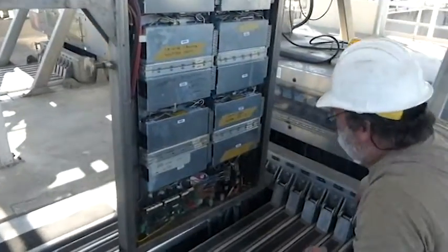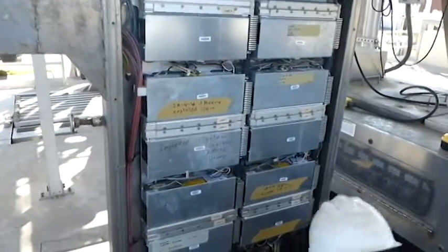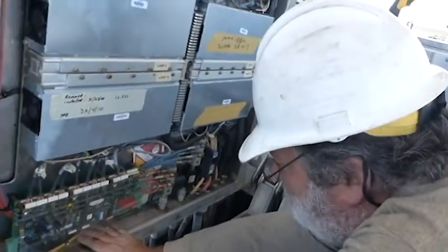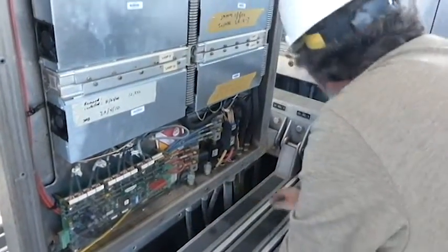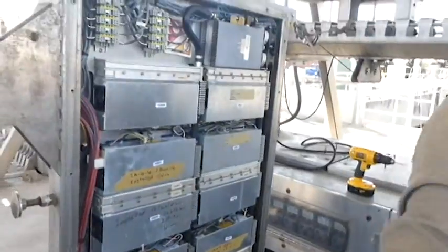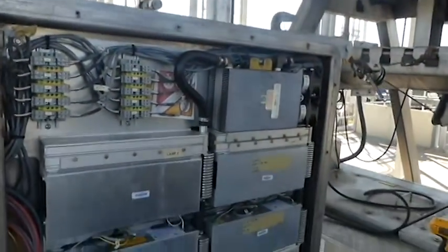As you can see, each watertight array has 10 ballasts installed, one for each ultraviolet bulb. In addition, there is a main control board and a circulating pump system for cooling the ballasts. These systems are controlled by an output device and are run at 100% 24 hours a day to ensure effective water purification.